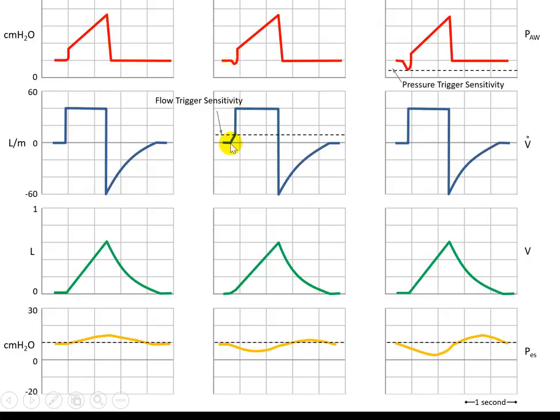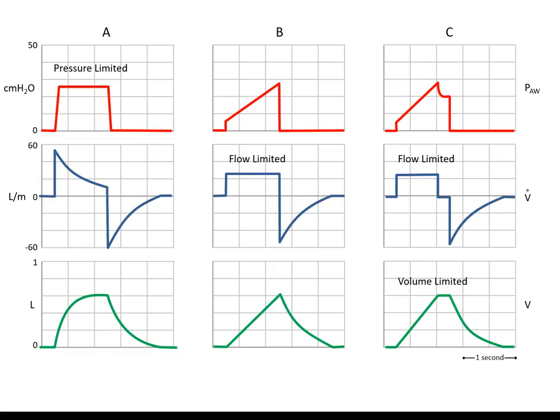In contrast, this breath here is triggered by the patient's initiation of effort. The machine is set to sense for any flow, and once this flow reaches a certain level set by the operator, the breath is triggered. In this other breath, it is also initiated by the patient, but the sensitivity is towards a pressure drop in the circuit. Once the patient creates a negative pressure reaching the set sensitivity level, that negative pressure triggers the initiation of the breath.